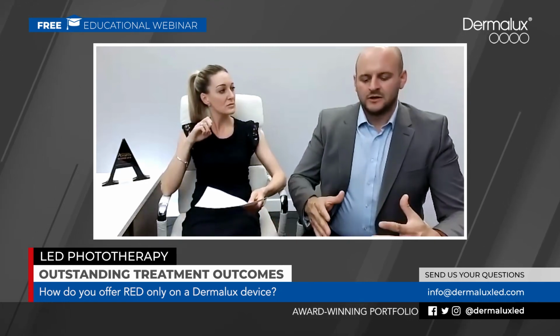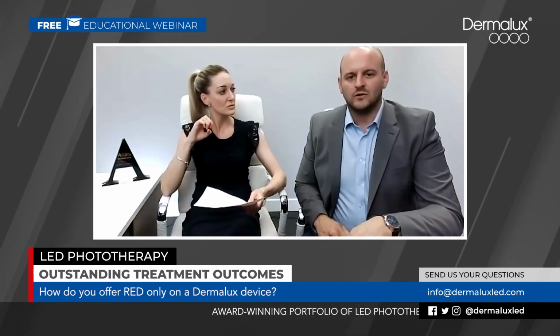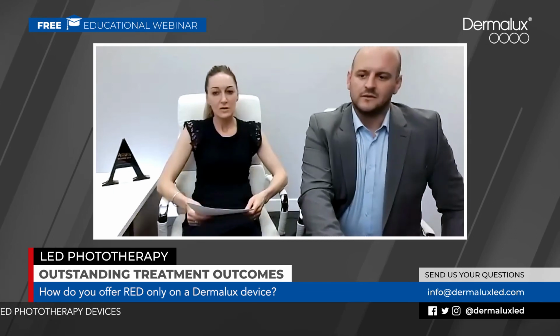The great piece of the Tri-Wave MD is that you have greater customizable options in the software, where you can choose whether you want 1, 2, or 3 colors on, and how long you want each of those colors to be on for. They don't all have to start from the starting point; they can be offset. So for example, if you wanted red on for 5 minutes and then you wanted blue and infrared to come on thereafter, you can set that up, and you can get them to turn off partway through the treatment. The maximum treatment time for the MD is 30 minutes with that option. So it all depends on what type of device you've got, but in short, yes, you can do single colors.